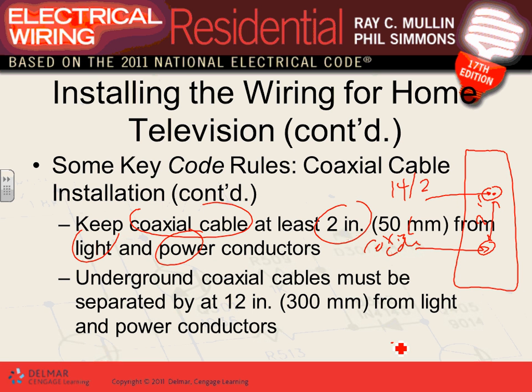If you're doing this underground with a trench: here's my trench, here come my power cables, and I separate them by 12 inches, then put the coaxial cable at the top. If you put them in the ground in a trench, you need that 12 inch separation. Later, when we lay out the site and bring power to the building, if you use the same trench for power and low voltage, that's okay, but you put power at the bottom, then go up 12 inches and put your low voltage cables above it.